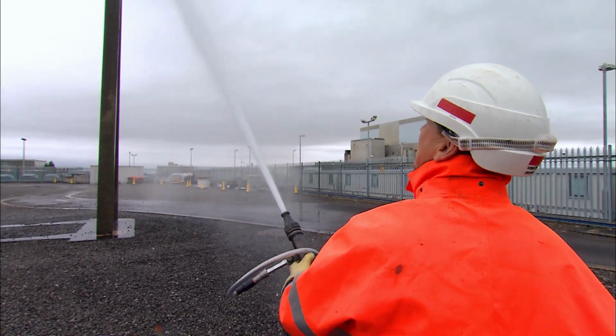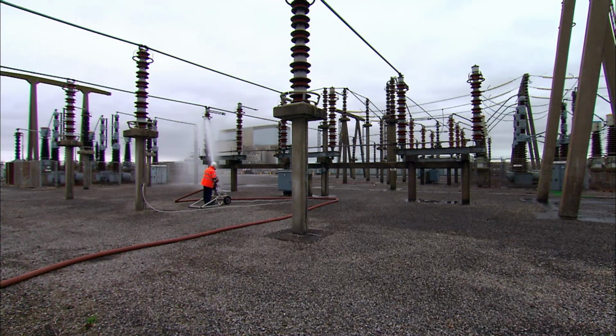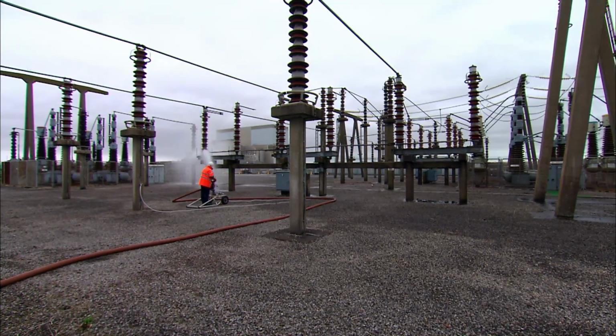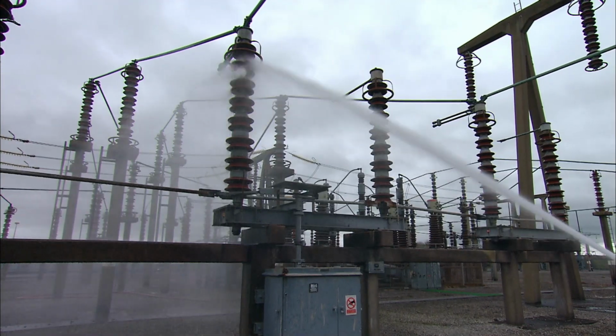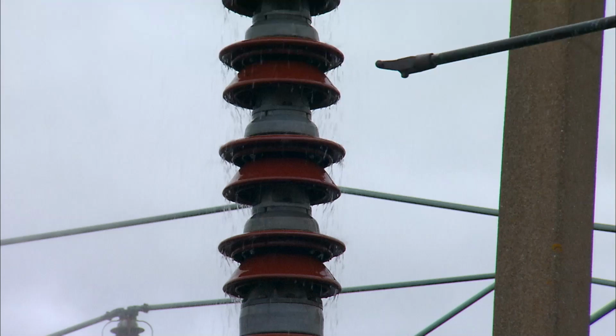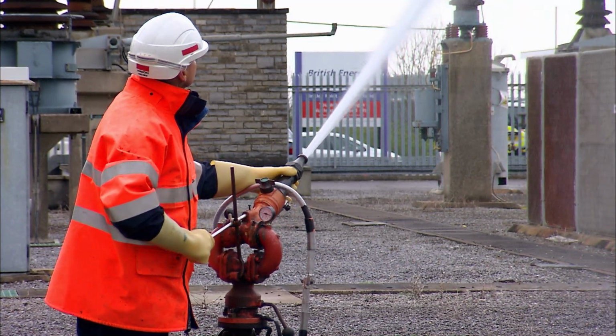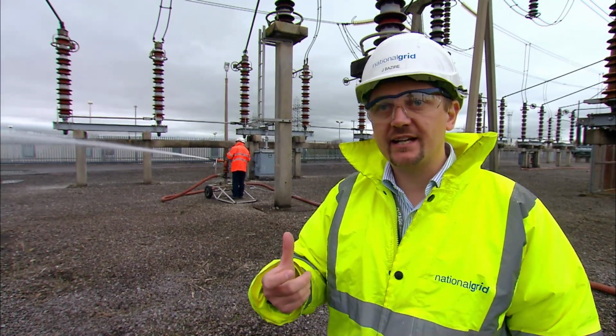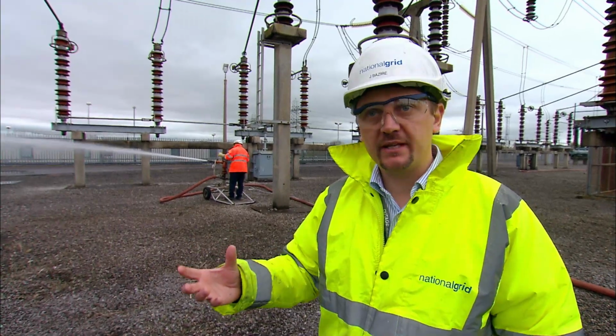That's just a bit of air in the pipe, that's nothing to worry about. Pete's checked the wind direction so that spray from the wash only blows onto insulators he's already cleaned. If it landed on salt-covered insulators, the spray would become salty and dangerously conducting. The water that's jetting out of there is coming out at a pressure of about 80 psi. And with the nozzle, it's all been calculated that it forms very fine droplets.